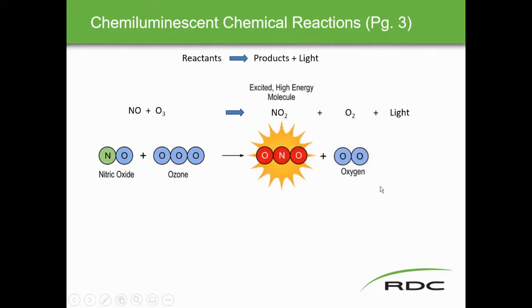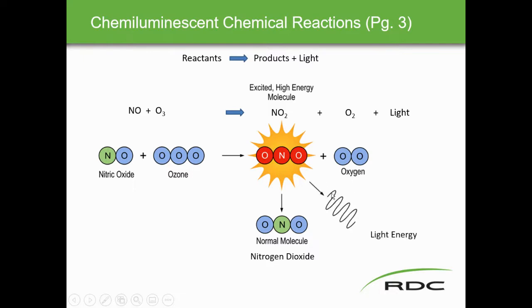In chemiluminescence, reactants produce products plus light. In this case, nitric oxide (NO) and ozone (O3) react to produce nitrogen dioxide (NO2) plus oxygen, and emit light energy. The amount of light energy is proportional to the amount of nitrogen dioxide in the sample — that's the key reaction this analyzer measures.